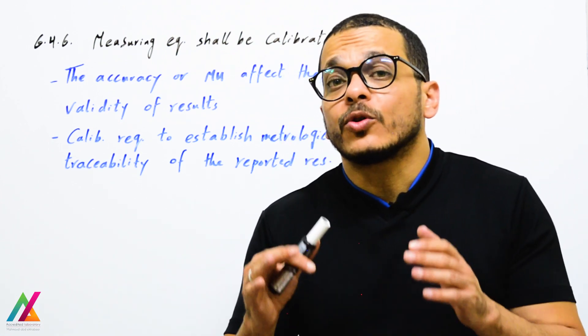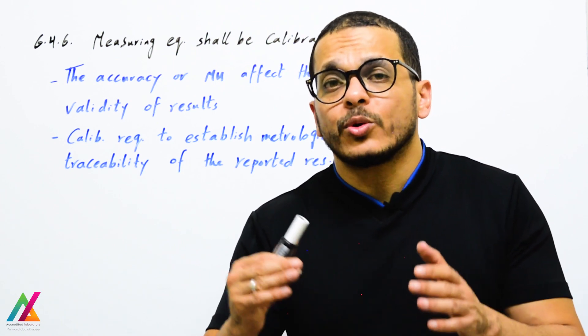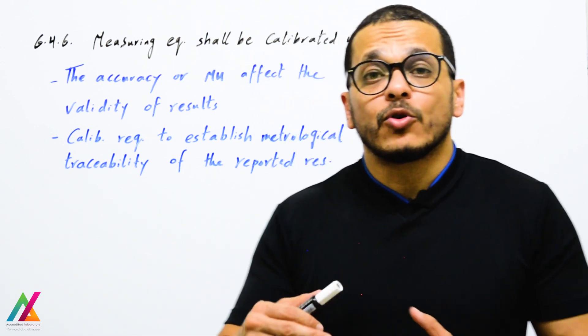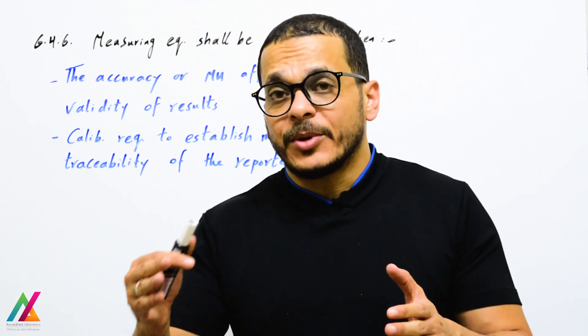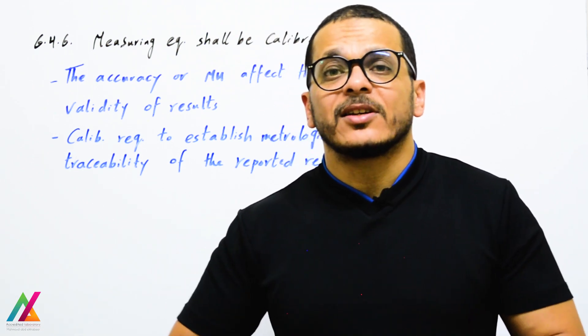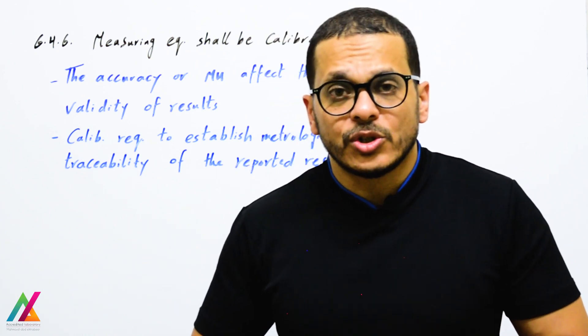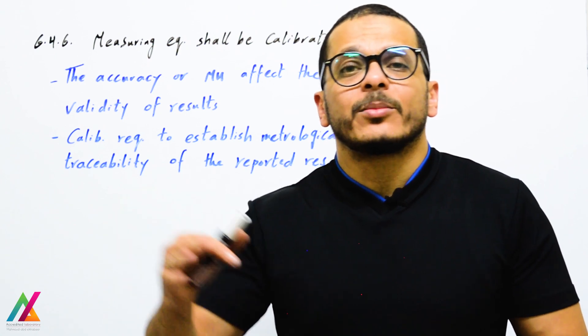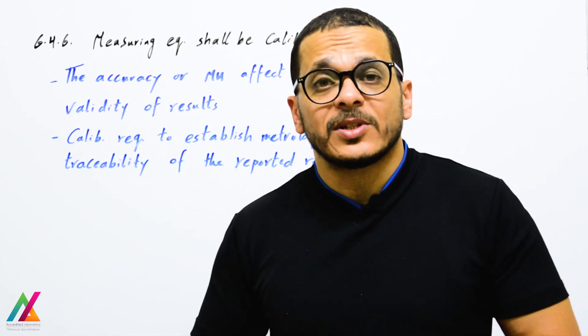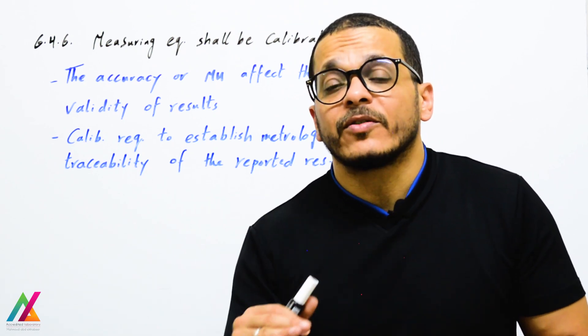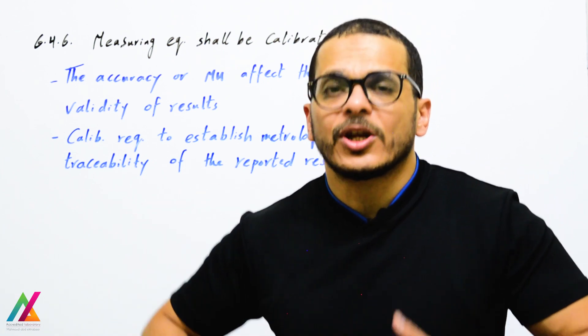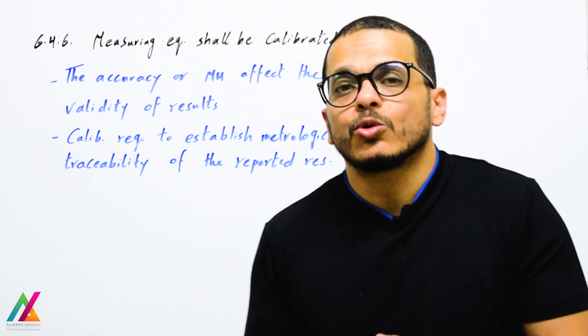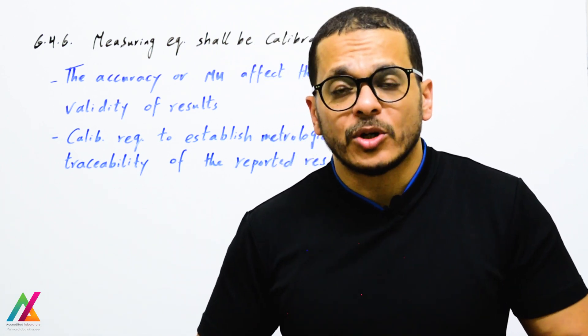Measuring equipment shall be calibrated when accuracy or measurement uncertainty affects the validity of results, and calibration is required to establish metrological traceability of reported results. Any measuring equipment shall be calibrated before use and acceptance criteria must be met — for instruments this includes slope and verification standard checks. If acceptance criteria are not met, recalibrate. For auxiliary apparatus, external calibration by a competent calibration lab is also required to establish metrological traceability.